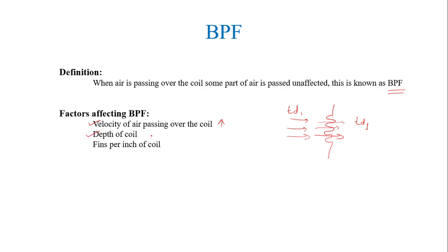The second factor is the depth of coil. In the side view of the coil, the length from one end to the other is known as the depth of coil. If the depth is less, the bypass factor will be more, because when the depth is less, the air is in contact with the coil for less time. Obviously, if you increase the depth of the coil, the bypass factor will decrease.